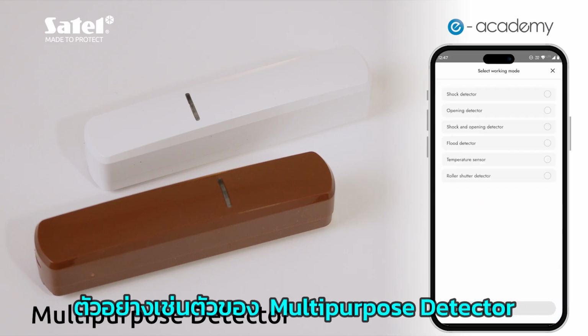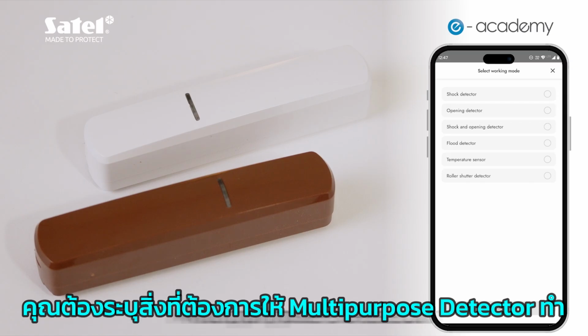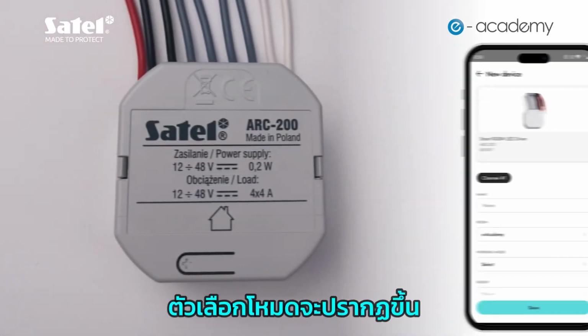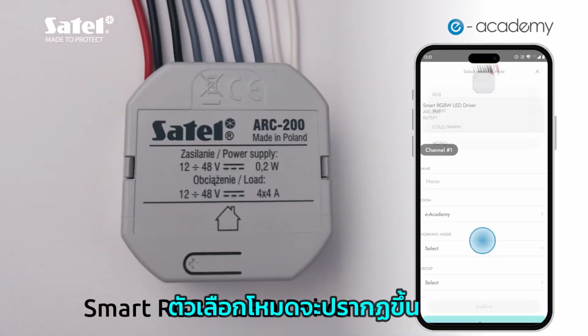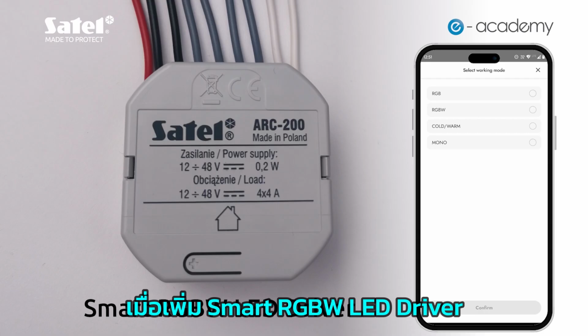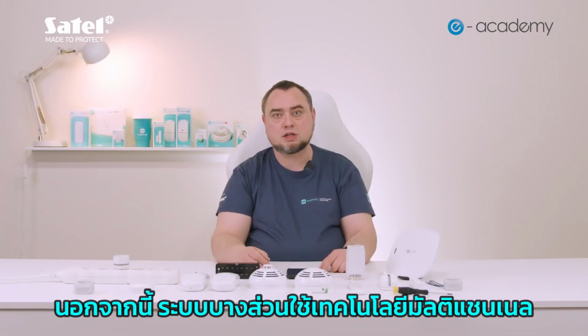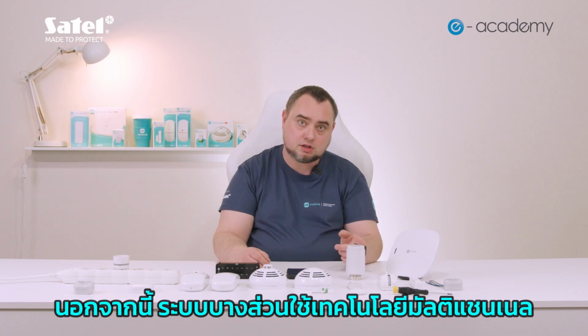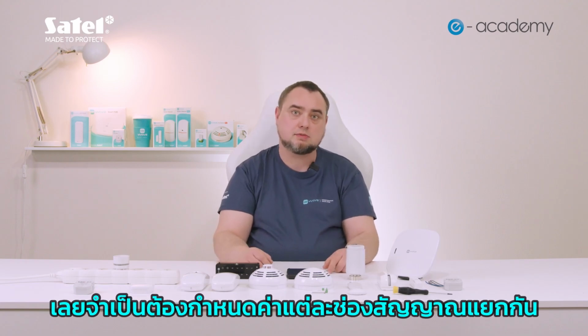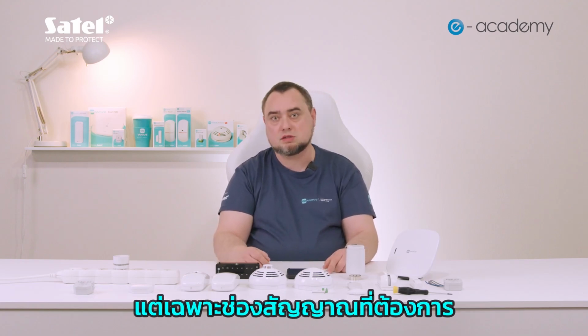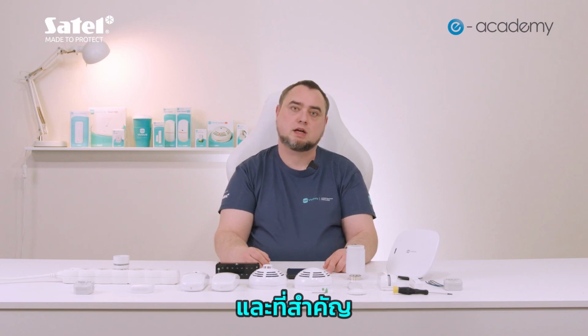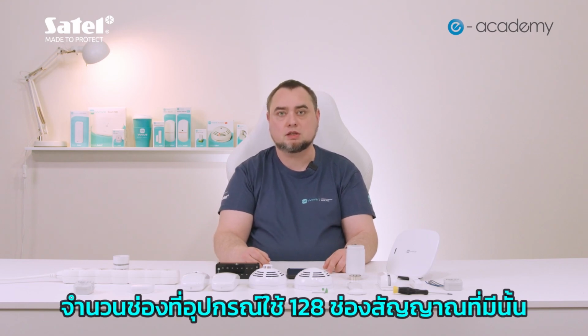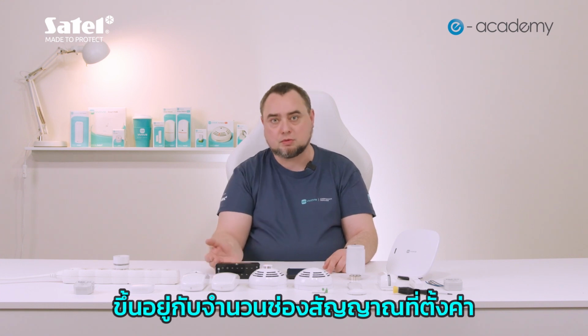This is the case, for example, with the multi-purpose detector, where you have to specify what you want it to do. The mode selection option will also appear when adding the Smart RGBW LED driver. Additionally, some system components use multi-channel technology. In that case, each channel needs to be configured separately, but only for the channels you want to use. And here is an important point. The number of positions a device uses out of the 128 available depends on how many channels you configure.